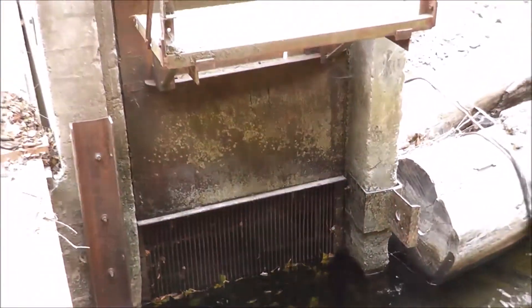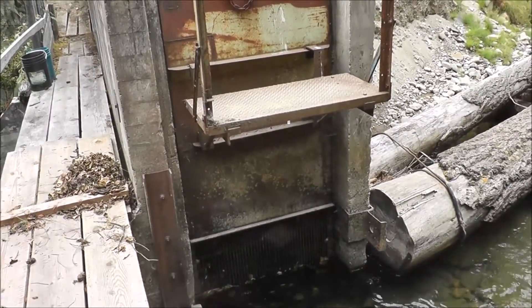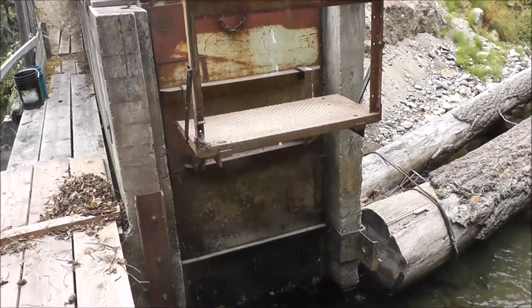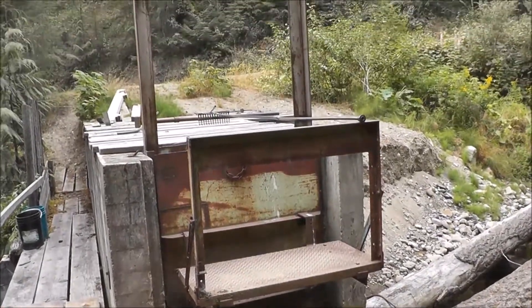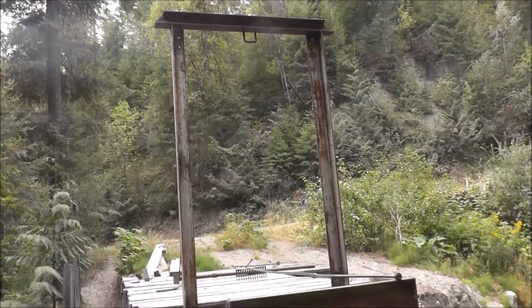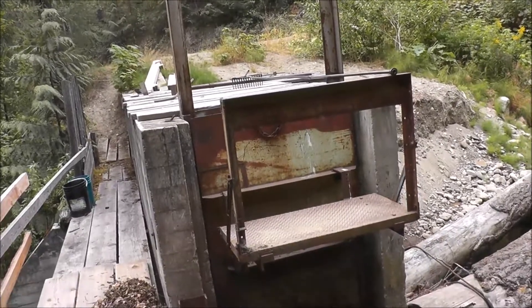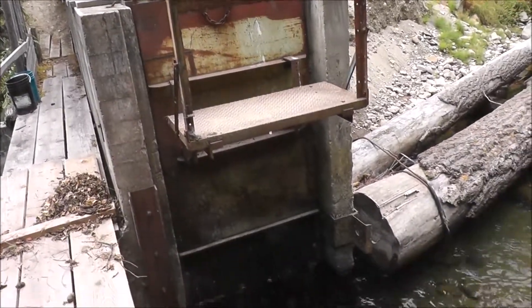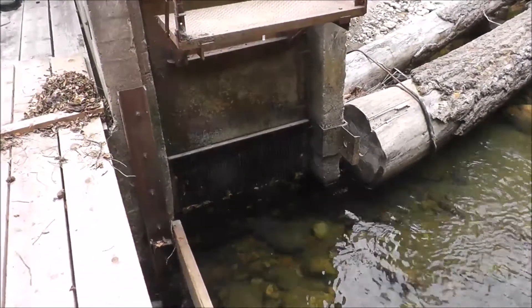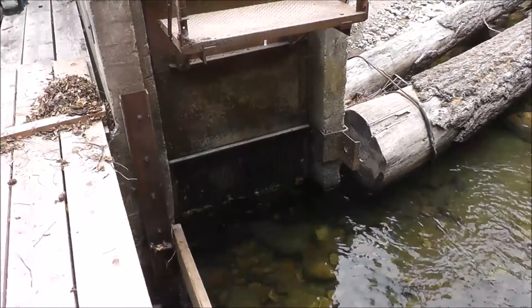If we come up here, you'll see a steel door — actually a place that you can stand on there. There's a steel framework up above so you can put some sort of a winch on there, and lower that door — take the screen out and lower the door right down. That stops the water if you have to do maintenance inside, and stops the water from even going into the pipe to do repairs.